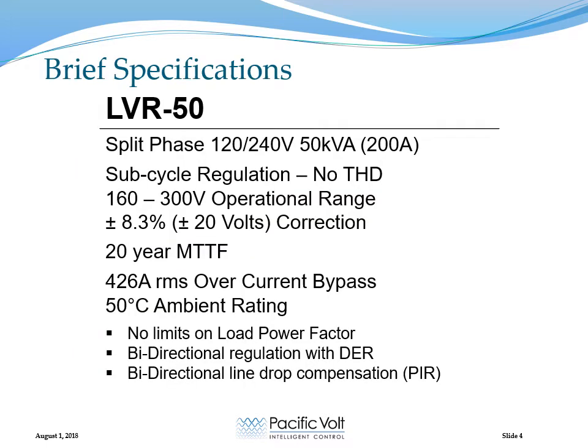The LVR50 has true subcycle regulation. It creates no total harmonic distortion. It will operate with an input voltage range between 160 and 300 volts. It provides a plus or minus 8.3% correction, which is nominally plus or minus 20 volts. It is designed to have a 20-year mean time to failure. It's also designed for a 50 degrees C ambient rating.